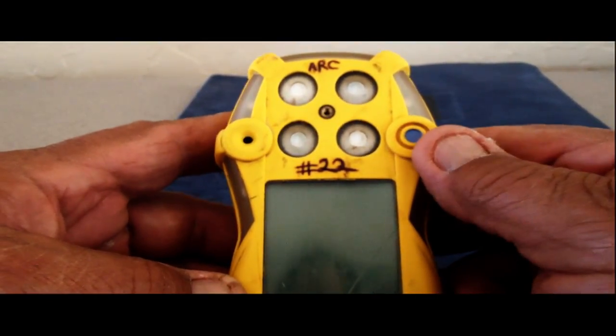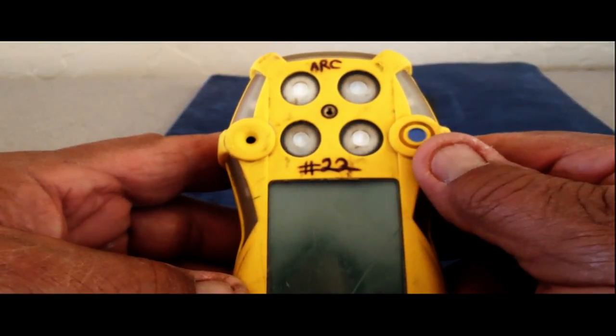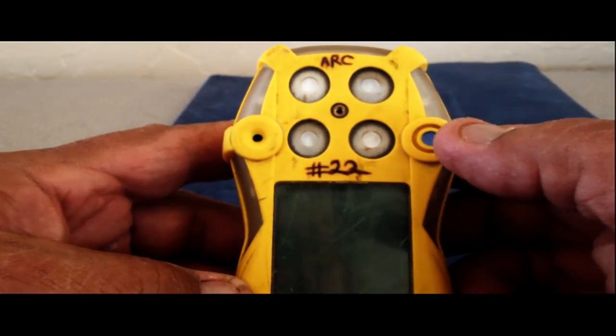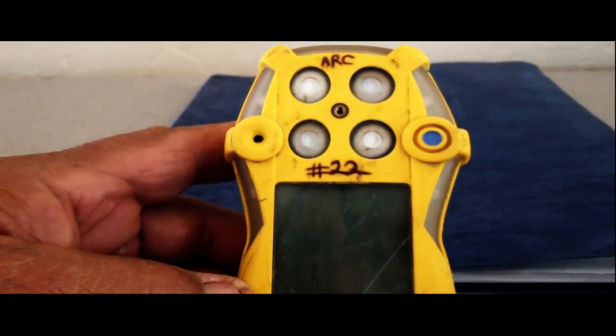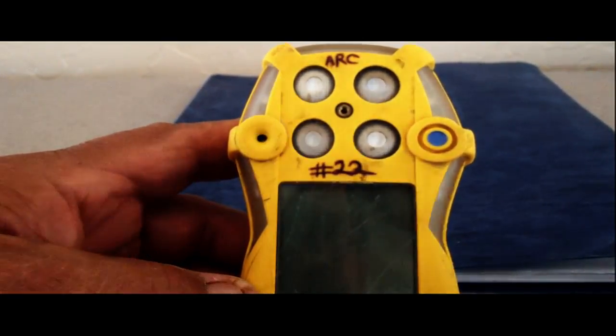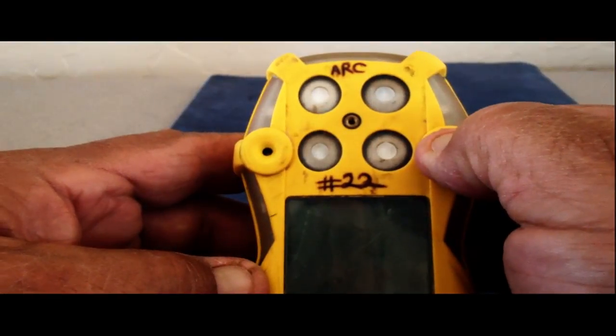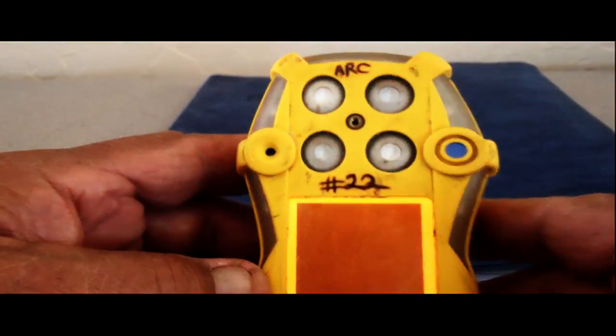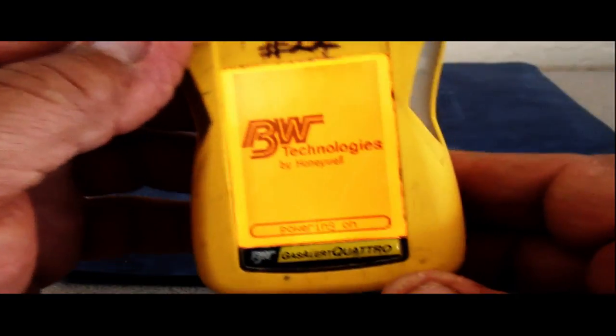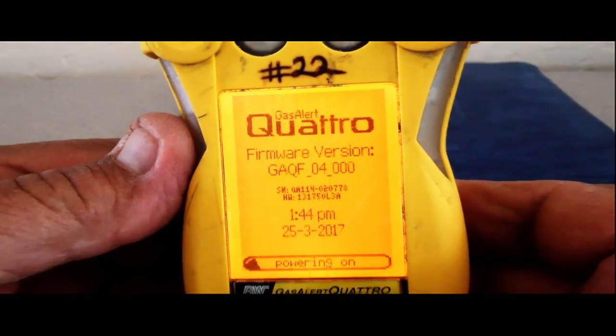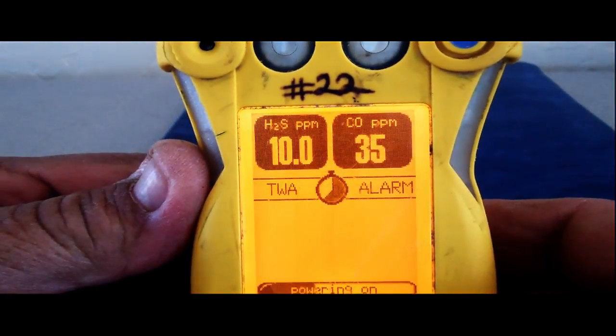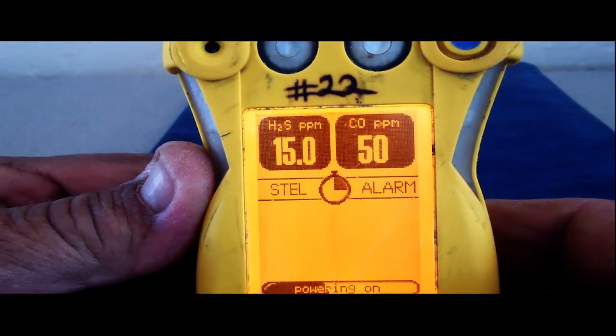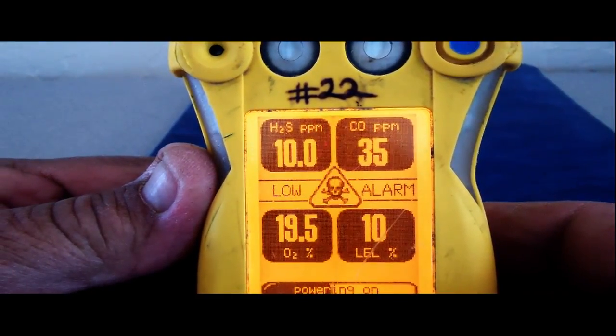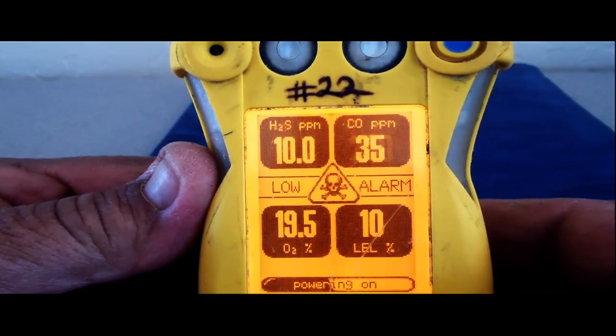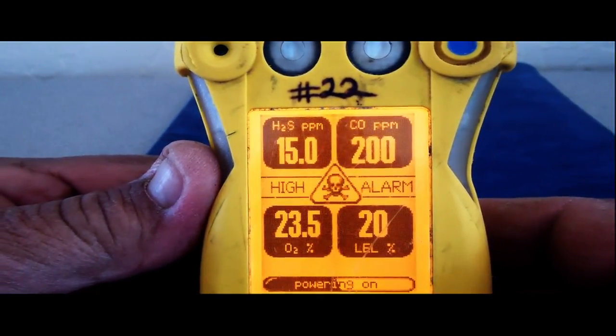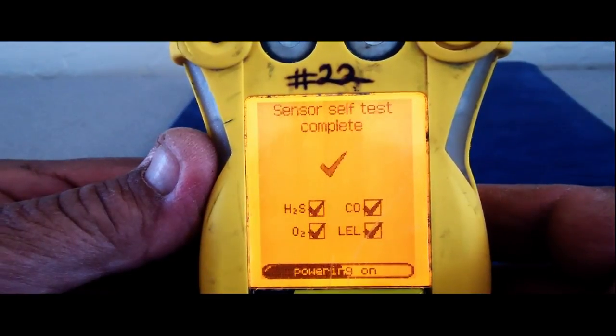First off, I'm going to turn it on and we'll watch the startup phase as it checks the sensors and does a little fresh air setup and tells you what, if anything, is wrong with your meter. So here we go. Push and hold. On she goes. And it is a QUATTRO, and it gives you the version. TWA alarms for your toxins, low alarms for the meter, high alarms for the meter, and basically just follow whatever it says on the screen.